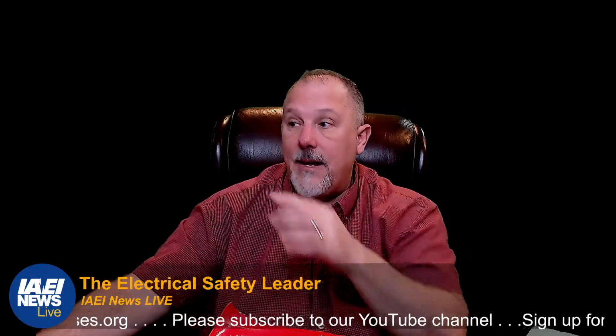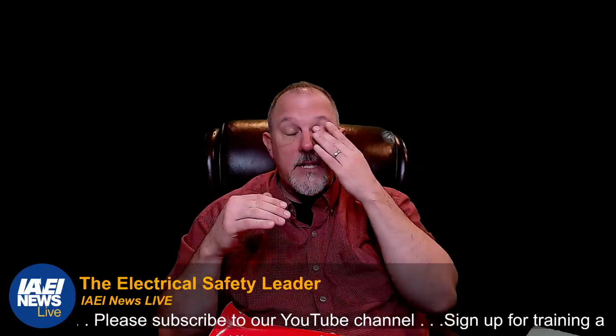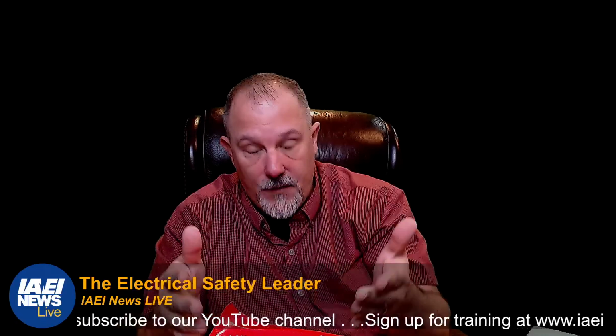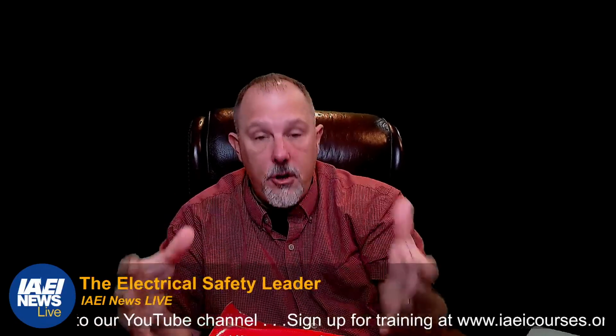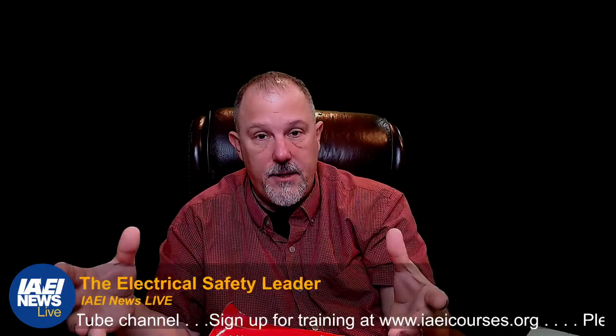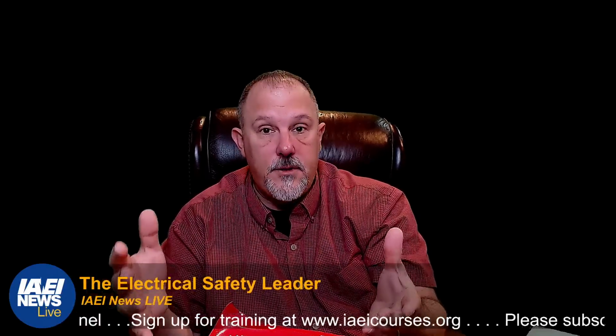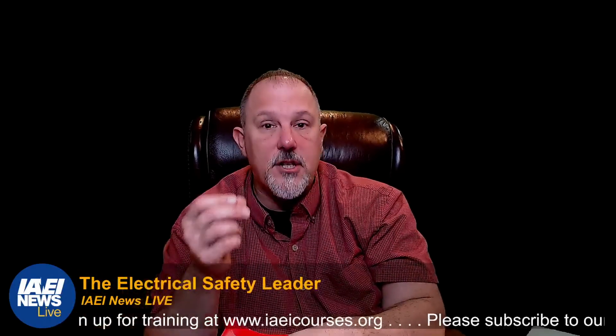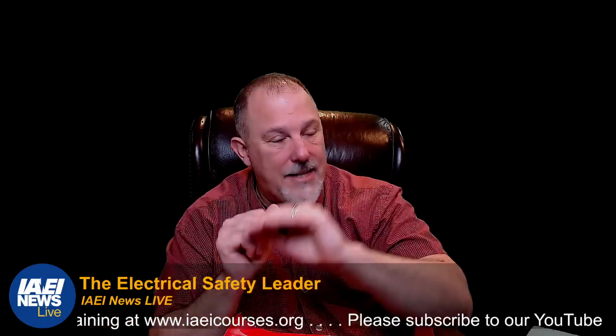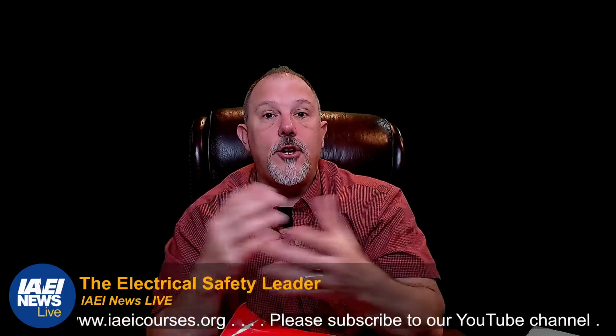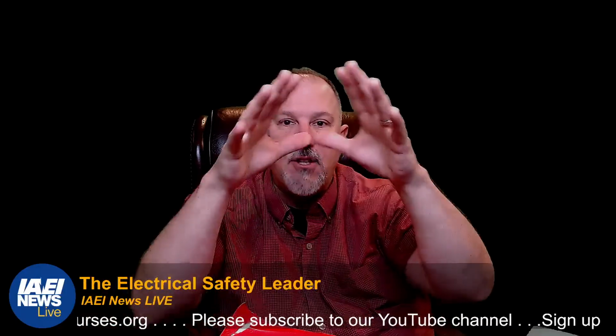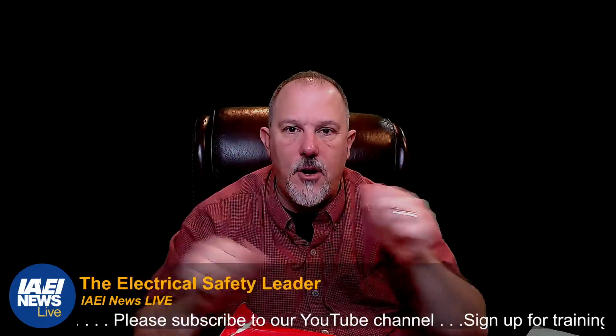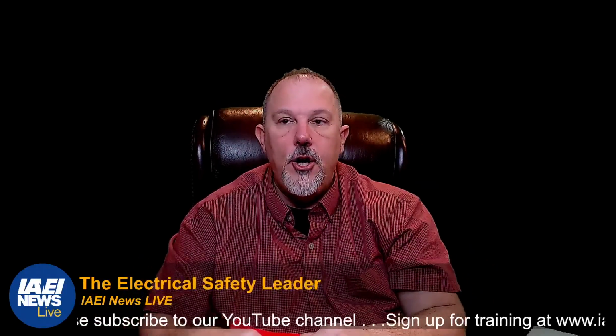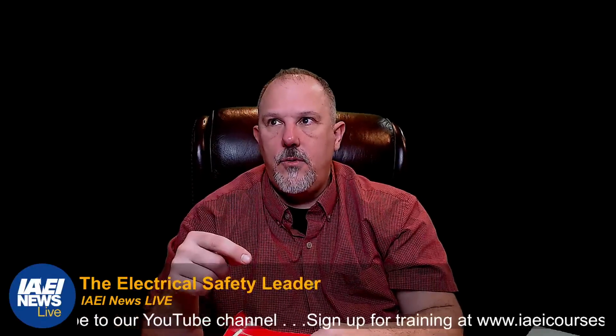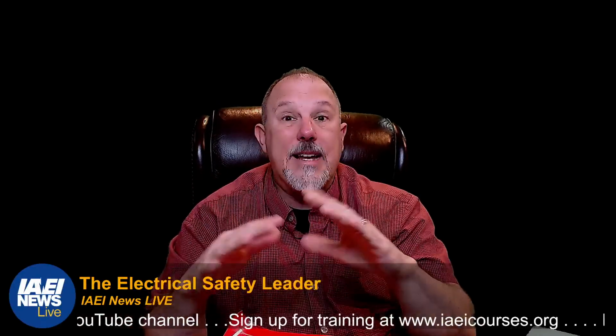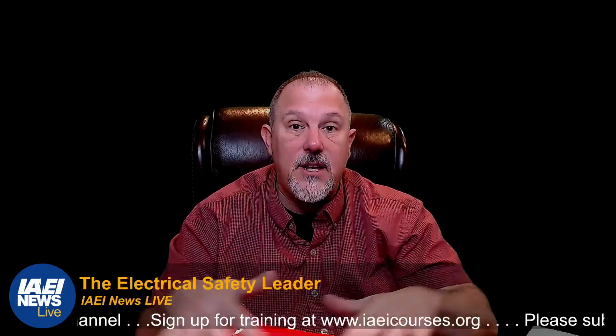That's it. So I think the takeaway of this is, if your panel board and enclosed panel board are in great condition, every 5 years, you're going to establish an electrically safe work condition on that panel board, take it out of service. You're going to take the dead fronts off. You're going to inspect all of the breakers. You're going to turn the breakers on and off. You're going to cycle them. You are going to clean, make sure there's no dust in the bottom of the panel boards.